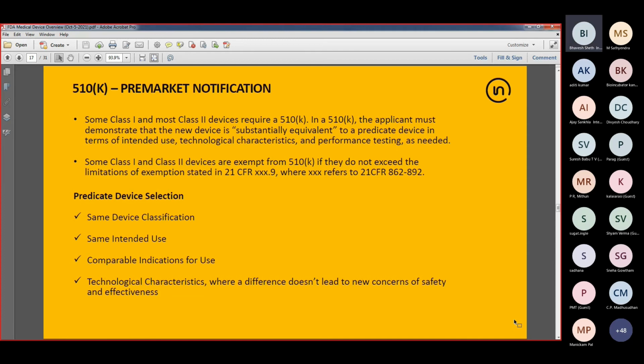should be comparable. And lastly, the technological characteristics. Depending on the type of product you're looking at, if it's a medical electrical product involving software, wireless capabilities, or if it's a non-electrical device, you could be looking at different attributes from a technological characteristic standpoint and the specifications. But the bottom line is, you'll have to demonstrate to the FDA through a thorough comparison that if there is a difference in some specification or technological characteristic, there is supporting data based on testing or a scientific rationale to demonstrate that such a difference won't lead to new concerns of safety and effectiveness. So that's the main aspect of the whole 510K submission.